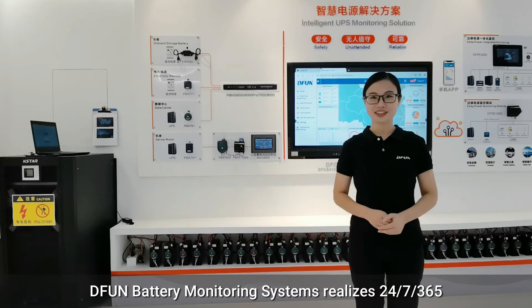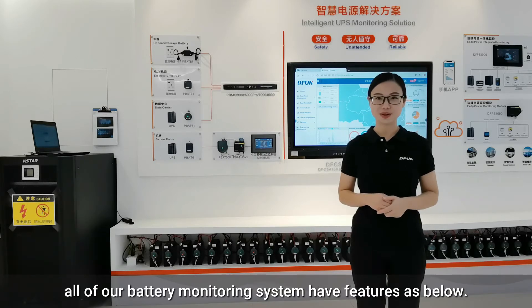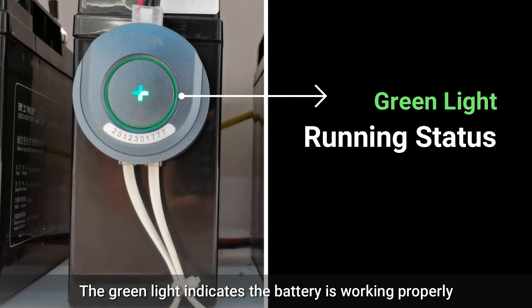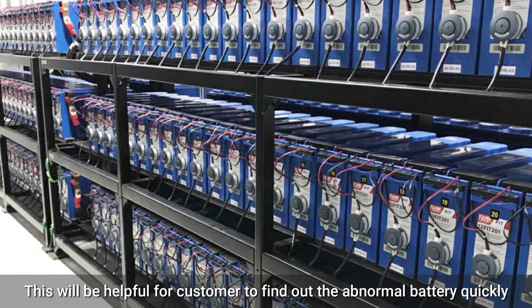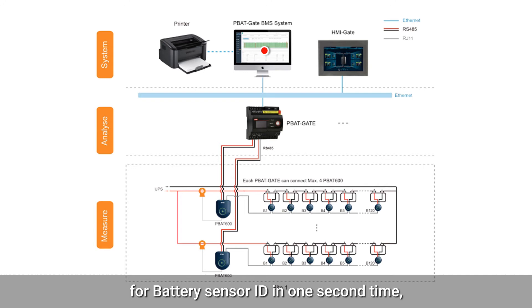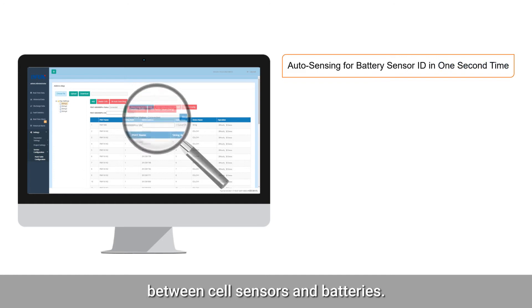DFUN Battery Monitoring Systems realize 24/7/365 monitoring of your critical backup batteries. All of our BMS have the following common features. The cell sensor has a unique design with a circular outward appearance and two-color LED lights. The green light indicates the battery is working properly, while the red light lets you know the battery is abnormal. This helps customers quickly find abnormal batteries among hundreds or thousands. Secondly, our BMS supports auto-searching for battery sensor IDs in one second, so engineers don't need to check and write them one by one — the system itself ensures a one-to-one match between cell sensors and batteries.